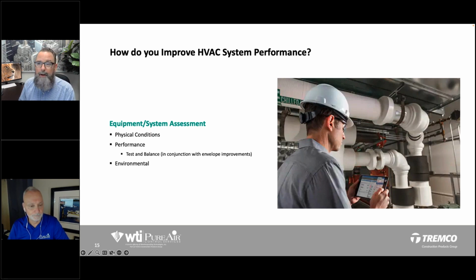Then what we start to look at is performance of the systems. Is it holding static? What does the thermal transfer off of the coils look like? Is it degraded? Is it being able to operate as designed? Is there leakage? As we discussed earlier, are the doors sealed? Are the plenums sealed correctly? And then again, when we talk about performance testing, if major work was done on the unit, or maybe new units were introduced or ductwork was rerouted, then we start looking at bringing in more of a NEBB like test and balance crew that needs to make sure that these new units are balanced with the old units. But mainly for an HVAC conditions assessment, we're not going to go to the extreme of what a T&B person would do.